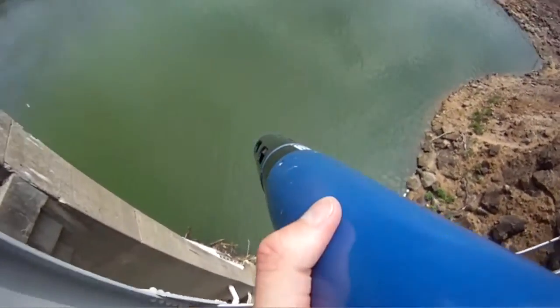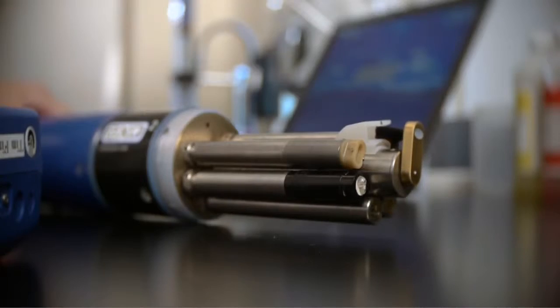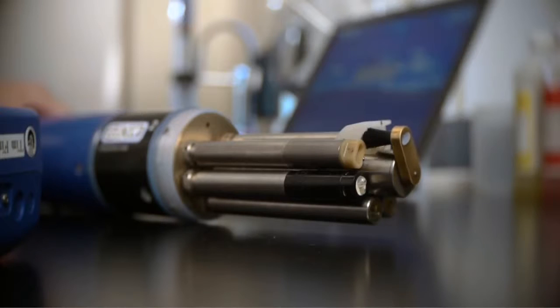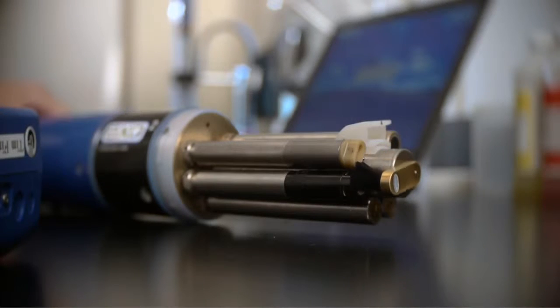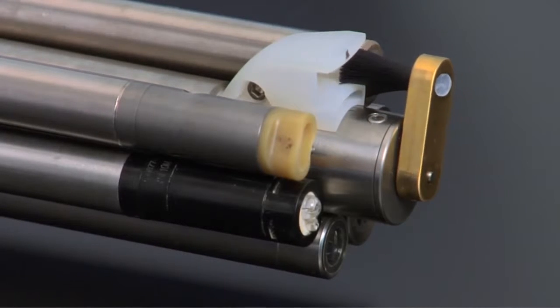So where I live along the Gulf Coast, the water's pretty nasty. There are a lot of places that my customers like to put their sondes that I wouldn't stick my large toe. There's a lot of biofouling. So being able to stick a sonde in the water for up to 90 days and not have that growth because of the central anti-fouling wiper is huge to them. This instrument can be out there for 90 days and the sensor faces stay clean regardless of what's growing on the body of the instrument.